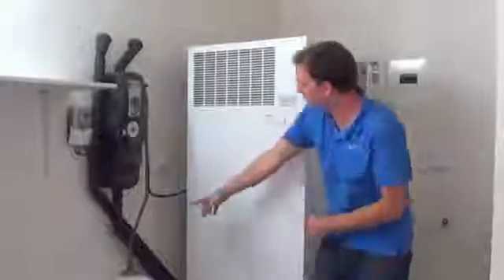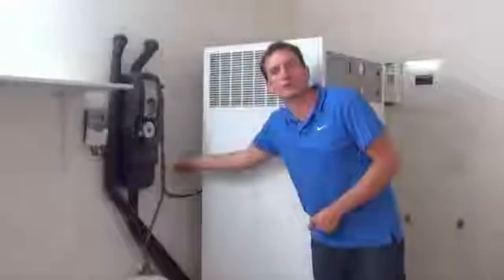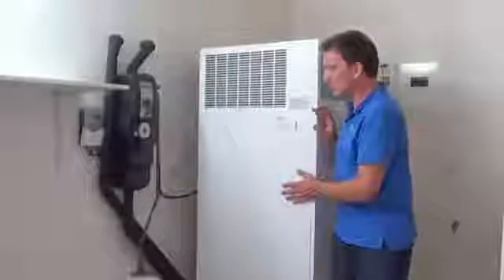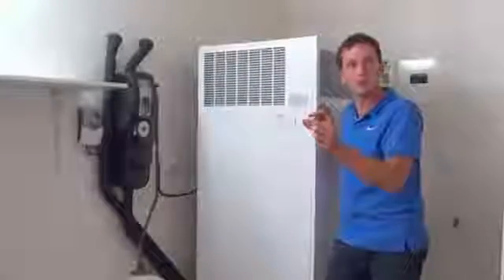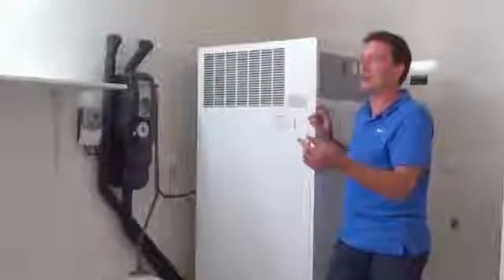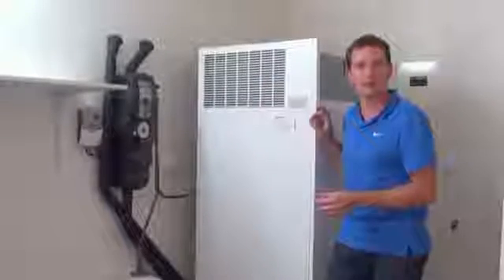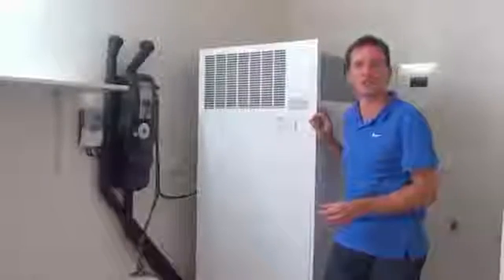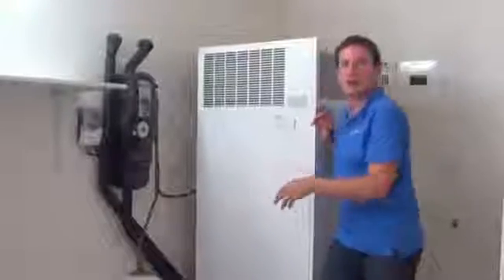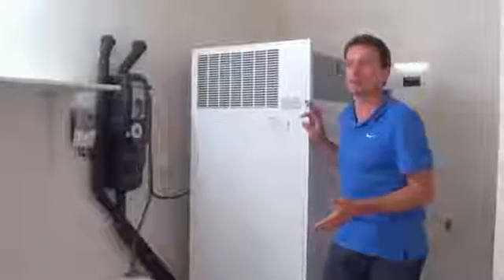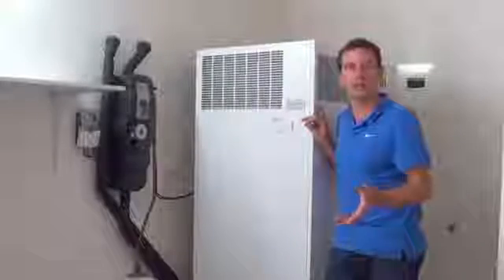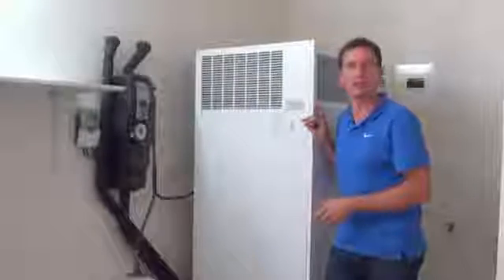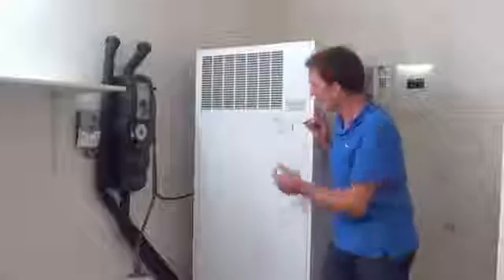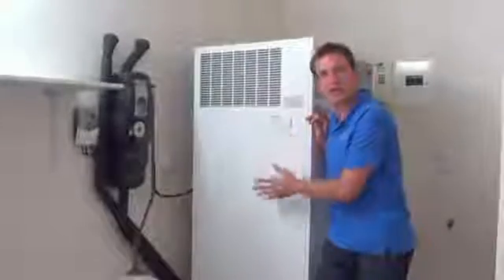This heat pump connects with a 3-pin plug here to the wall. When we import these machines, they actually come with a European 2-pin plug that you would buy if you buy a house light or a lamp or something else, or like a small fridge, a bar fridge. But with that we are heating up 300 litres. If you compare it to a South African local geyser, you would be looking at 3 kilowatts to heat up 150 litres. That is 3 times the power consumption, and this machine is doing double the volume.